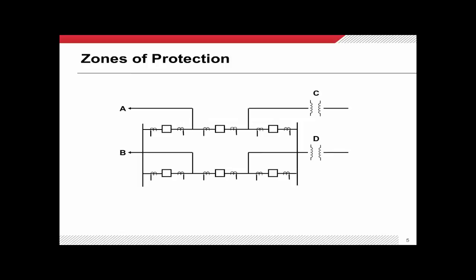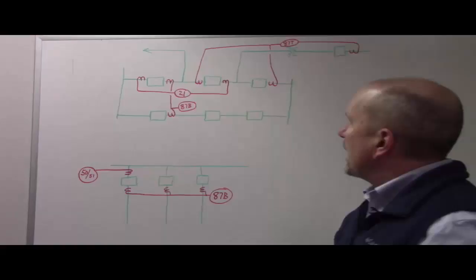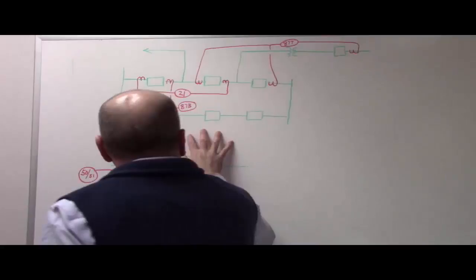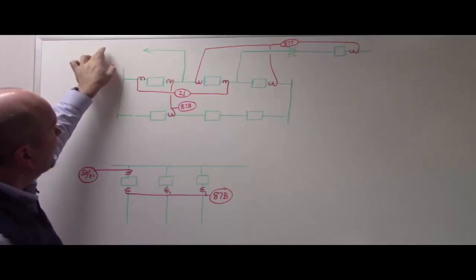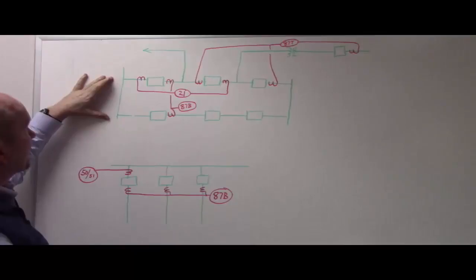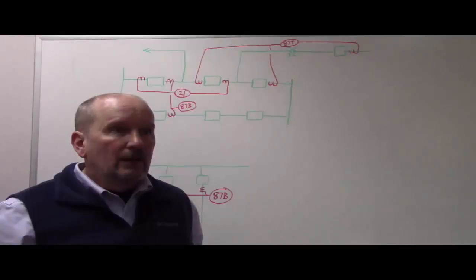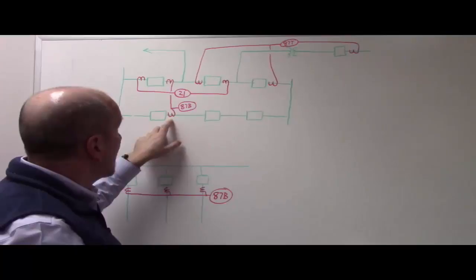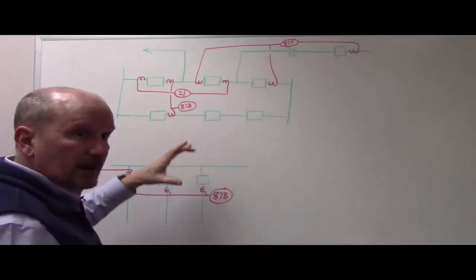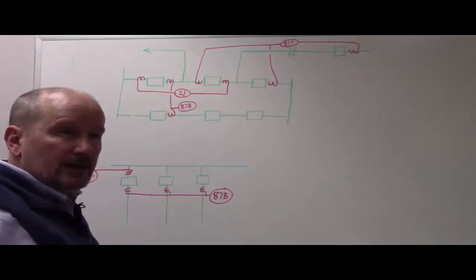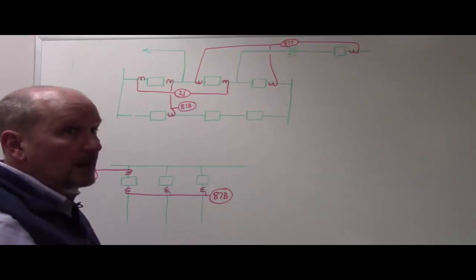Now I'd like to talk about zones of protection. On my whiteboard I have a breaker-and-a-half configuration with six circuit breakers. In my fictitious substation there's a transmission line going one direction, a transformer another way, and a bus being protected. In red are the AC circuits coming out of the current transformers — those little squiggles. This creates different zones of protection within our relaying scheme. Zones of protection are defined by where the current transformers are, and in modern dead tank circuit breakers they're closely associated with the circuit breaker.